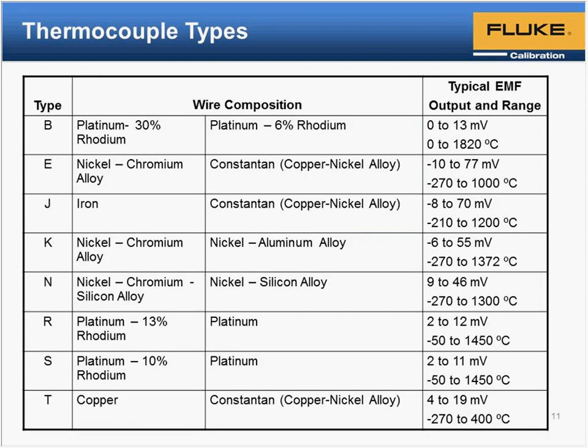Okay, the common letter types out there are listed here, with type K probably being the most common that I see. We'll talk about what the composition of the wire legs of these thermocouples are made out of. And then type R, these platinum and rhodium thermocouples.